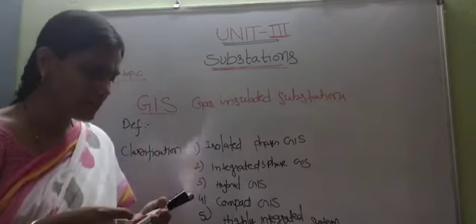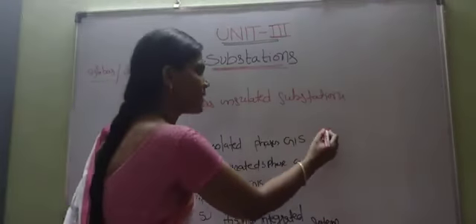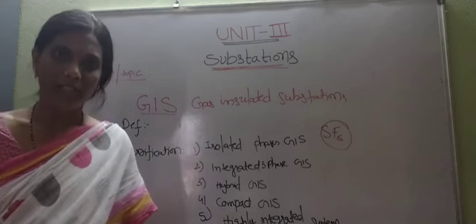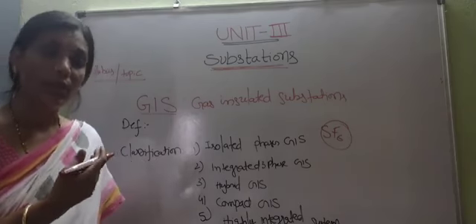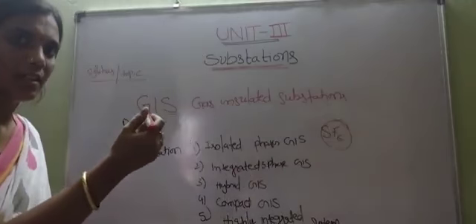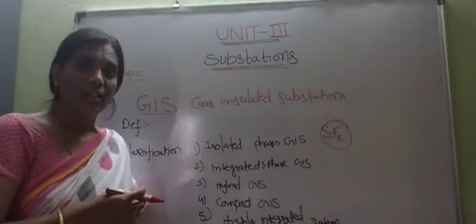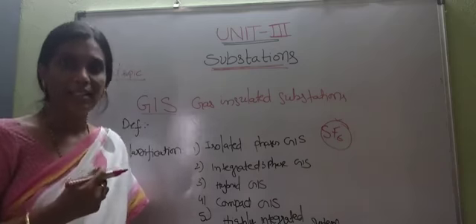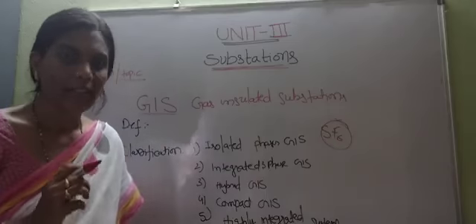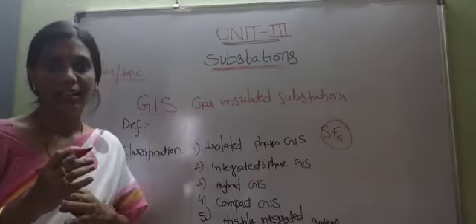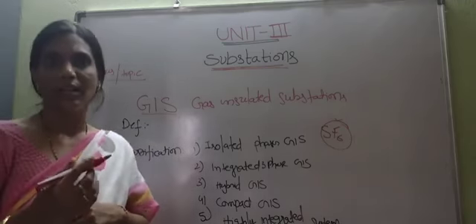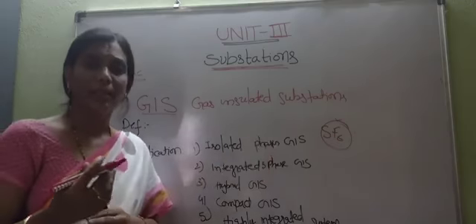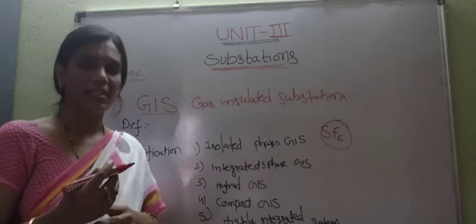GIS means gas insulated substation. Which gas are we using here? SF6. SF6 gas is being used here. Why this gas instead of air insulated substation, which is outdoor substation? Because it is coming under indoor substation. So why we are choosing SF6 gas insulated? SF6 is used as insulation in these substations. SF6 gas is having good thermal capability, high dielectric strength, non-flammable, non-corrosive, non-toxic, and highly inert. It does not easily react with other gases surrounding it. So these properties are why we are using SF6.